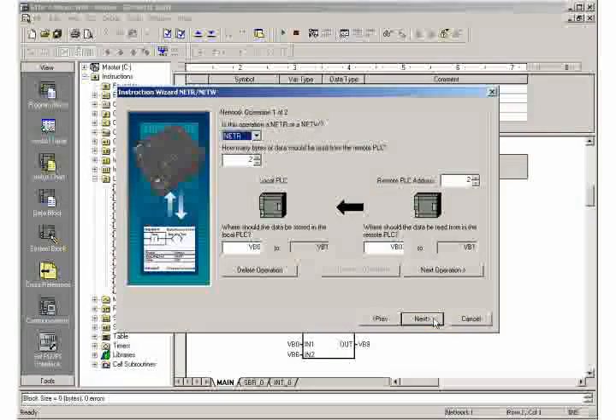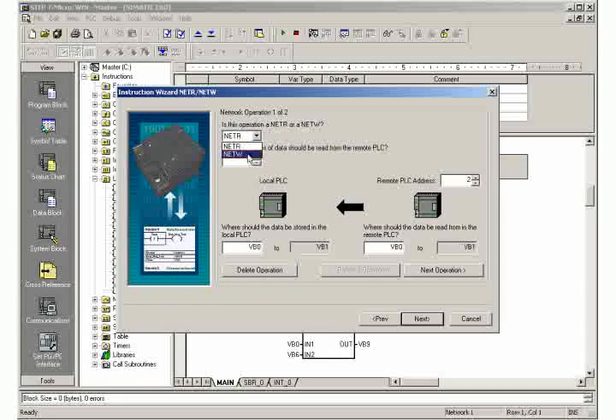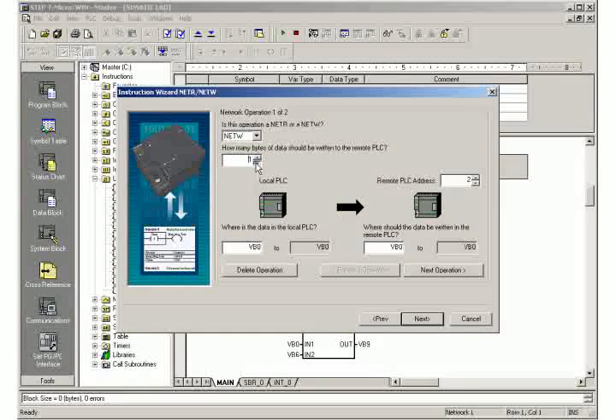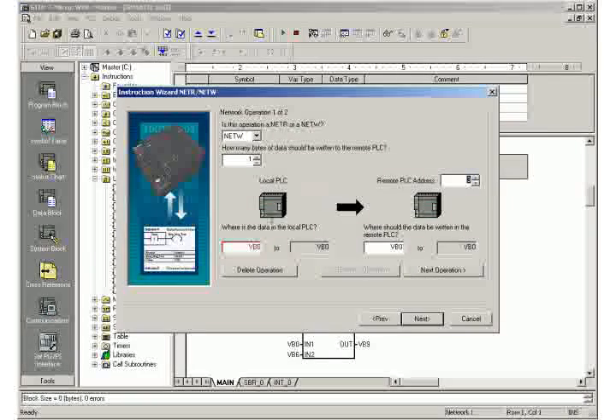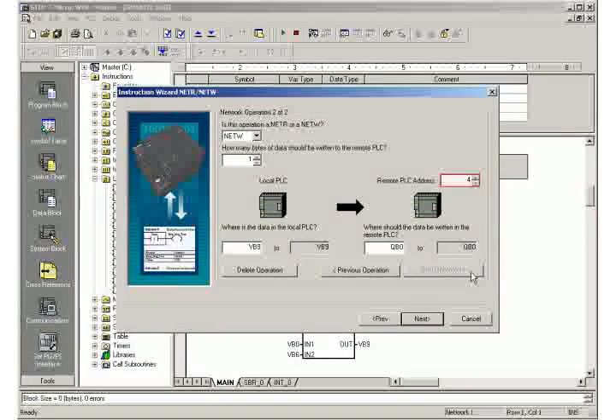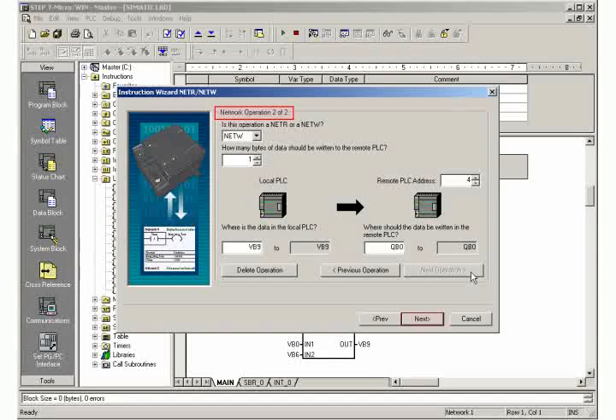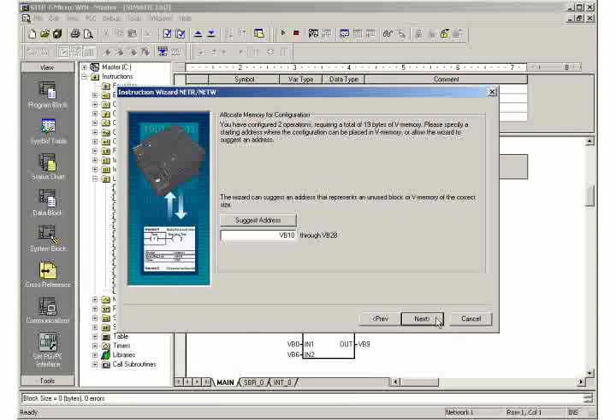Configure the first network operation for slave 1: operation NetW, write 1 byte, remote PLC address 3, local start byte VB8, remote start byte QB0. Accordingly, select remote PLC address 4 and VB9 as local start byte for the network operation with slave 2. Now select an unused V-Memory area for the network configuration and complete the instruction wizard.